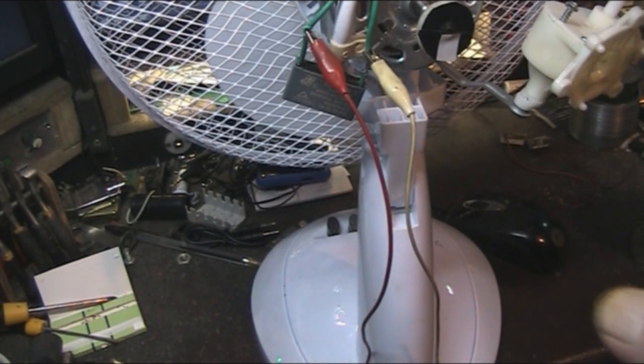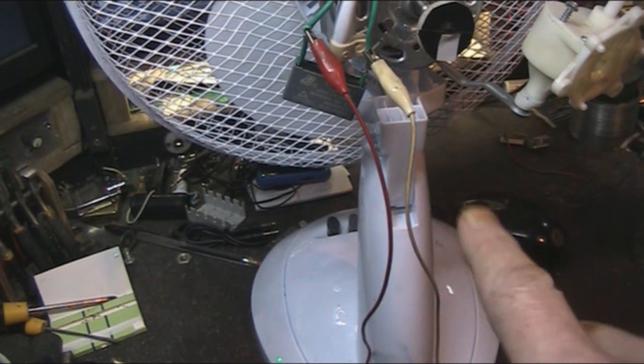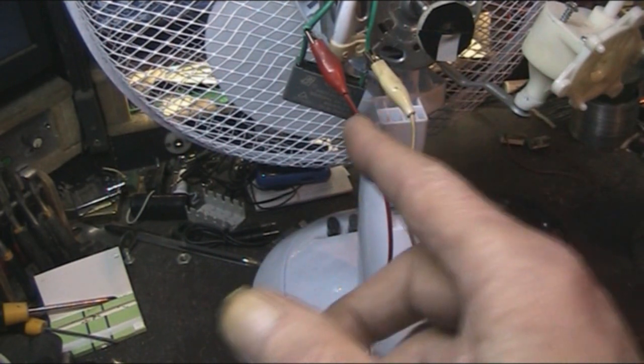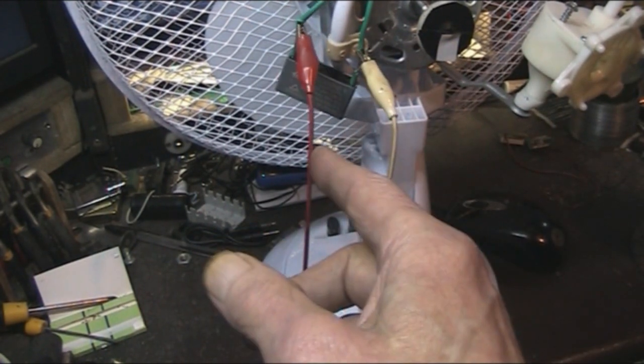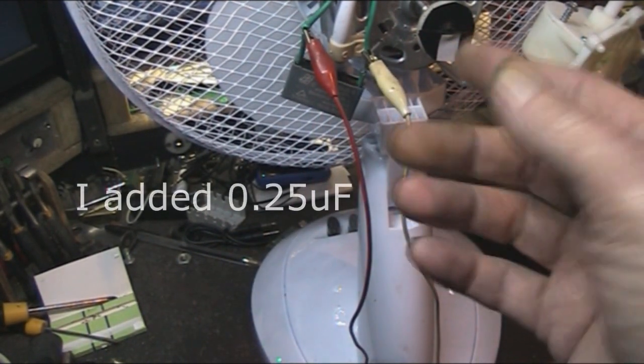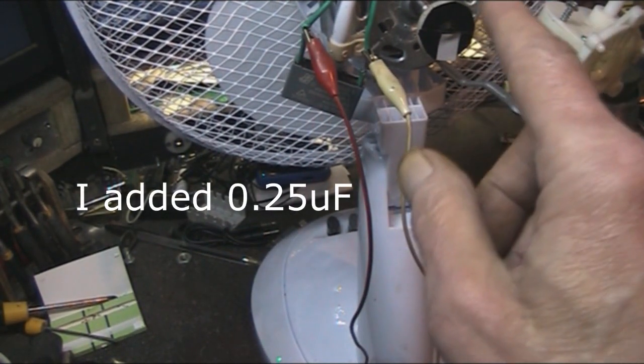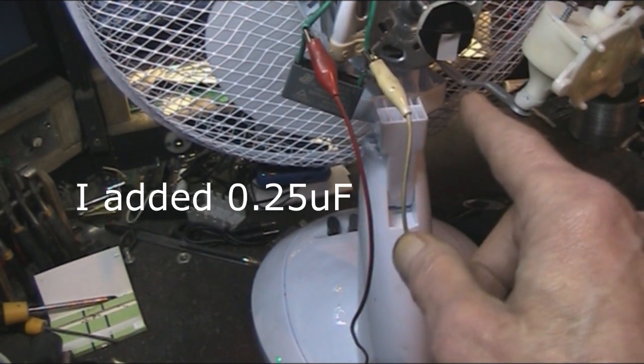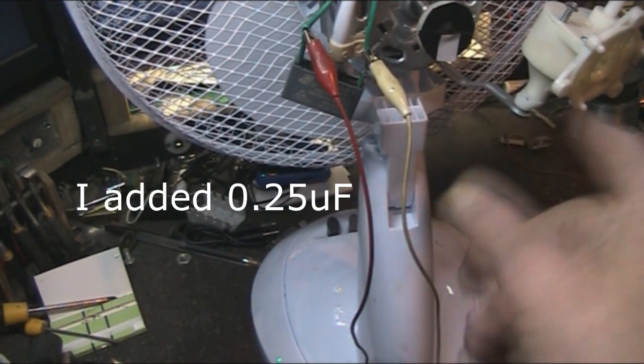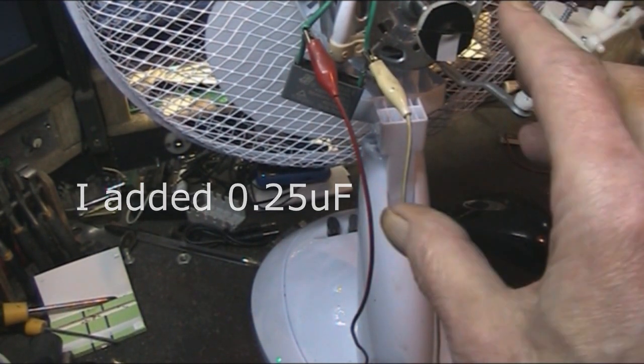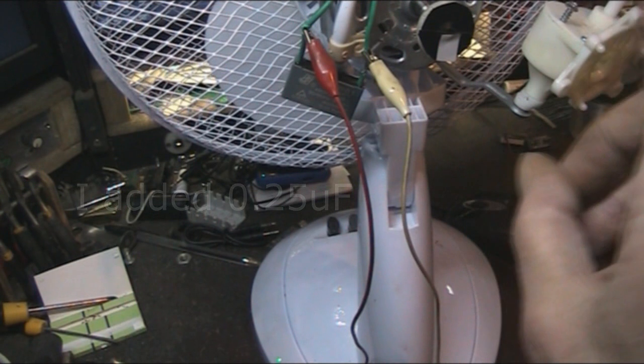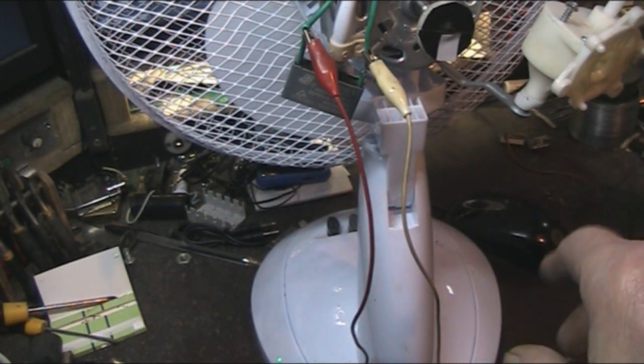Which is about right for a difference. If you're going from a 60Hz to a 50Hz, you need to make the fan go faster, or the motor go faster. So adding capacitance, which is what Techmoan would have done, would make the motor go faster, and bring it in line with using it on 50Hz.